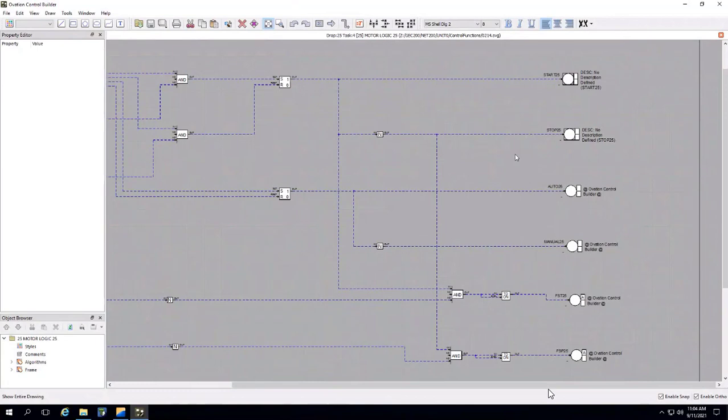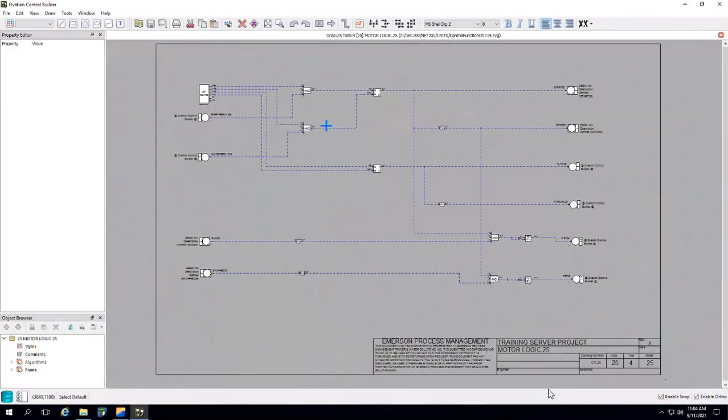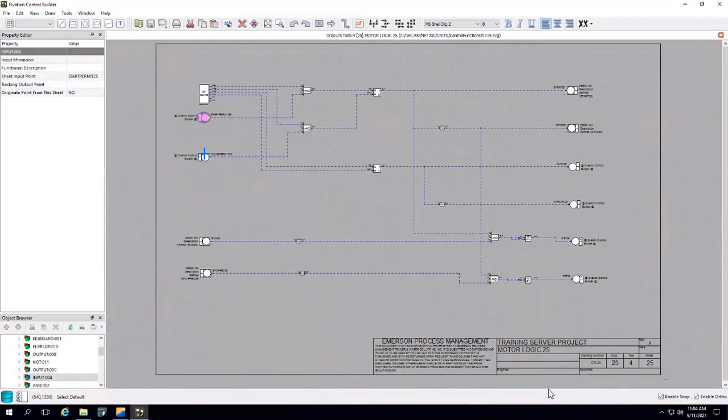Right? So Zulfikar and Muhammad Ahmed, everything seems to be fine. Only one issue. You have not defined the point descriptions for these points. I want you to describe the point description for all the points. Rest alarm is configured in a very good manner. And all the connectors seem to be fine. Name is perfect and number is good.